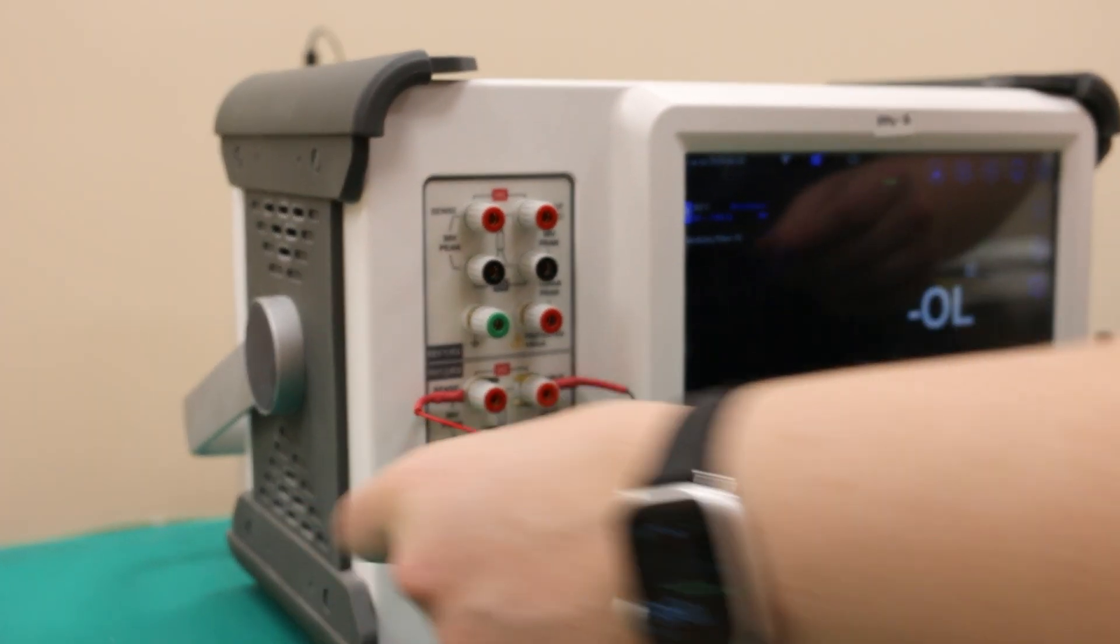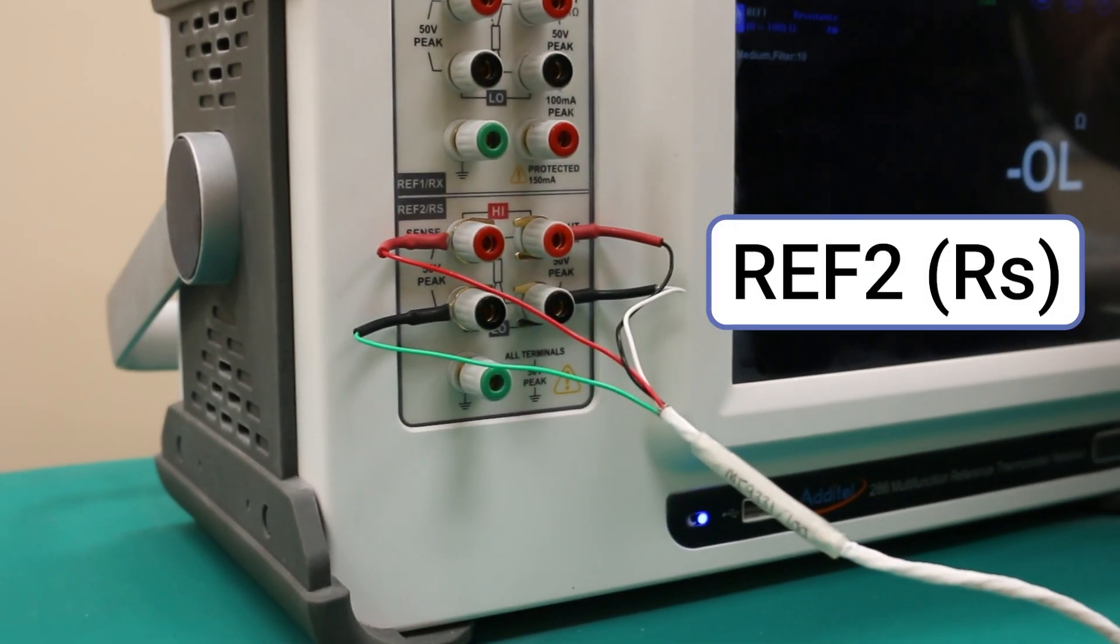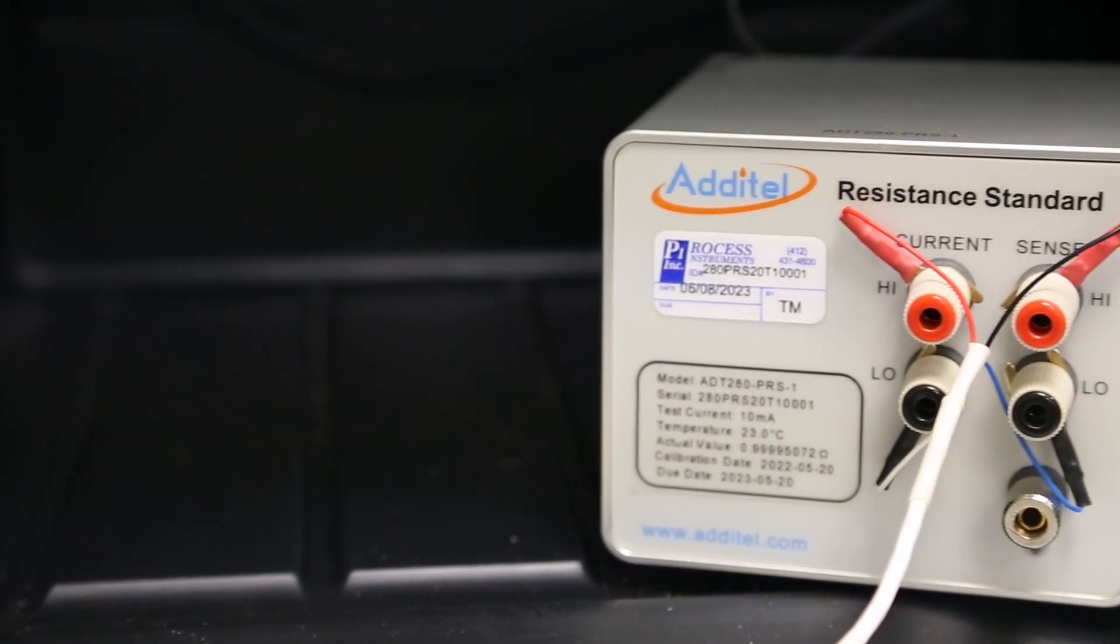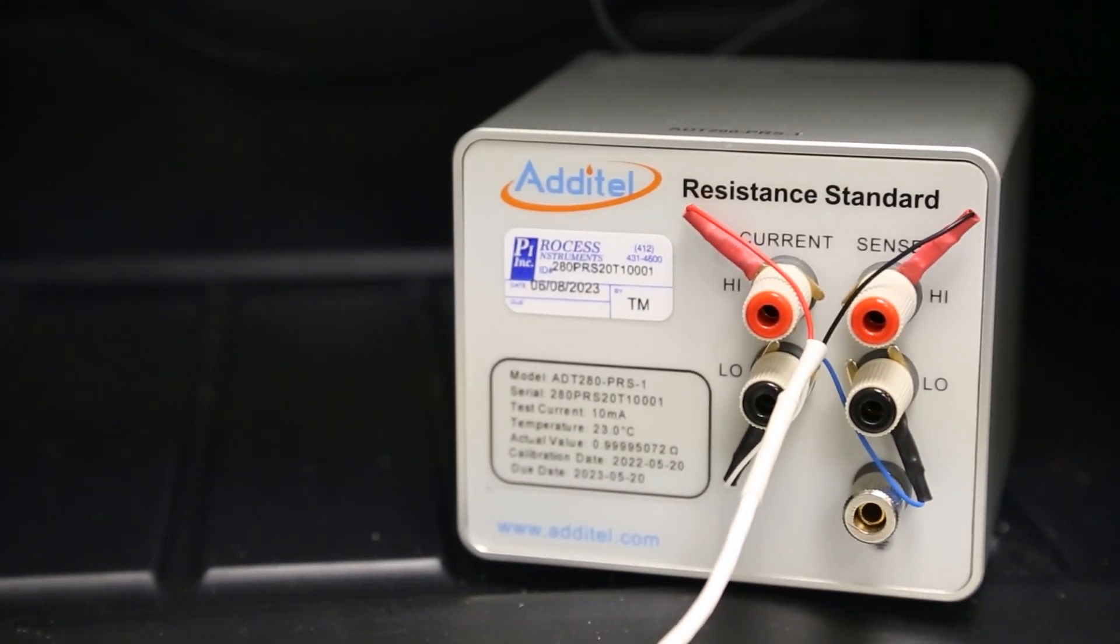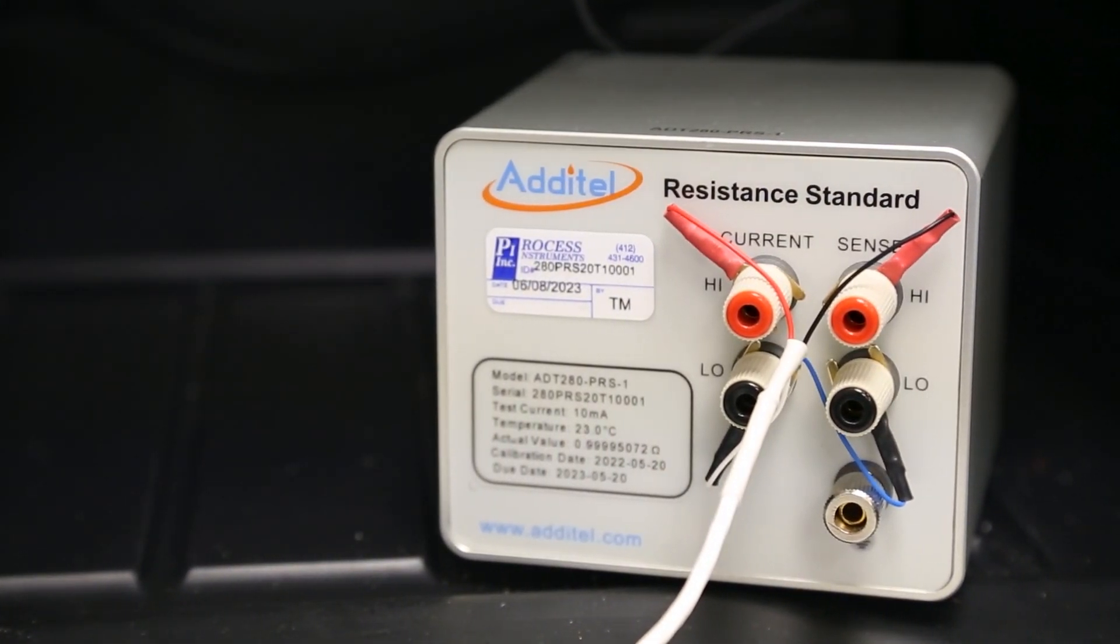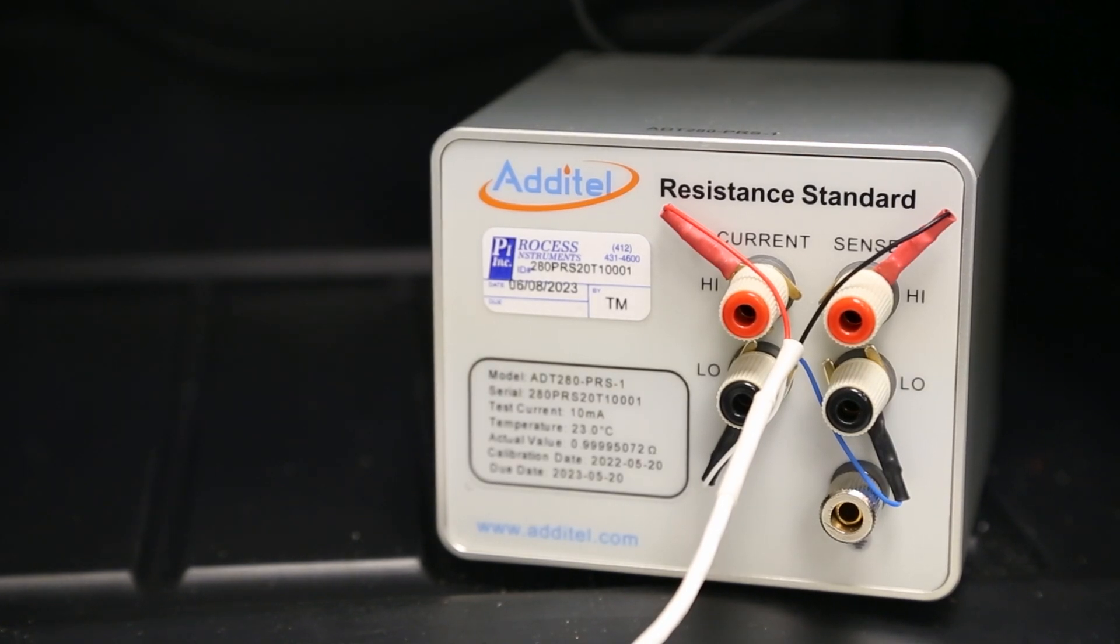To begin, we'll connect a reference standard resistor to the REF2 port on the 286. This 100 ohm resistor is stored in a precision temperature bath held at 23 degrees Celsius and will be used as an external reference to calibrate the five probes against.